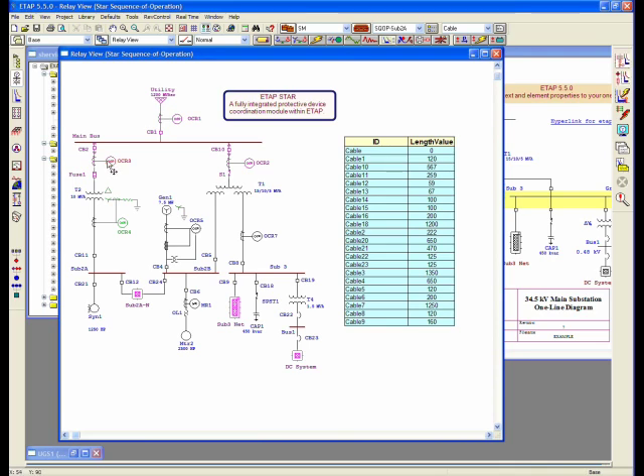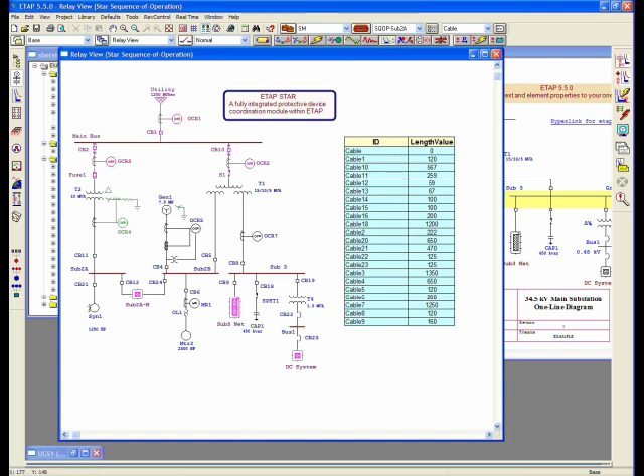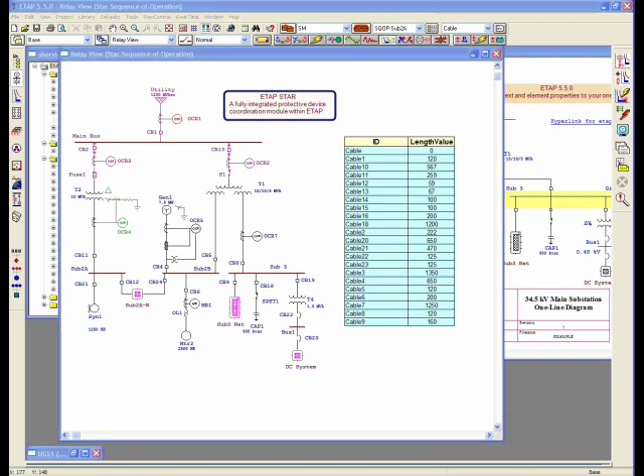Selecting an element and being able to select that element and showing the TCC curve. For example, if I was to select this relay, OCR1, I'll go ahead and highlight that for you. I'm selecting OCR1, and I'm going to click on this button over here, which is to create a new TCC.